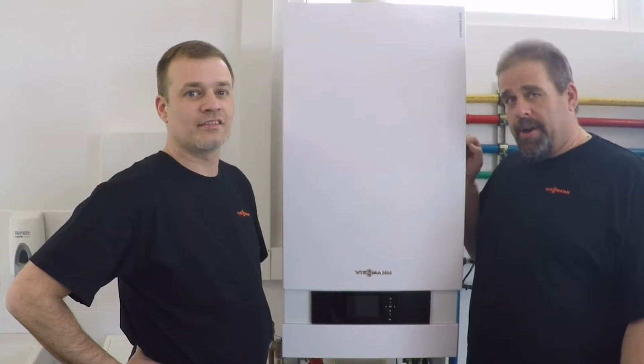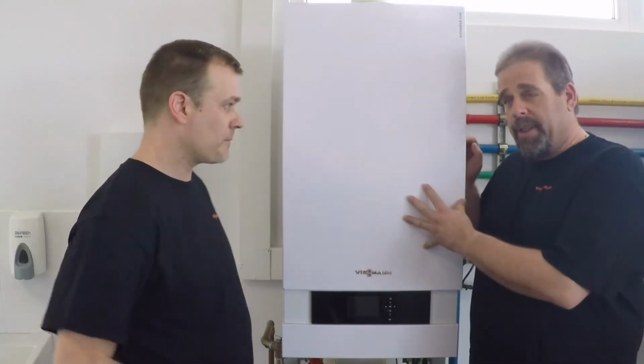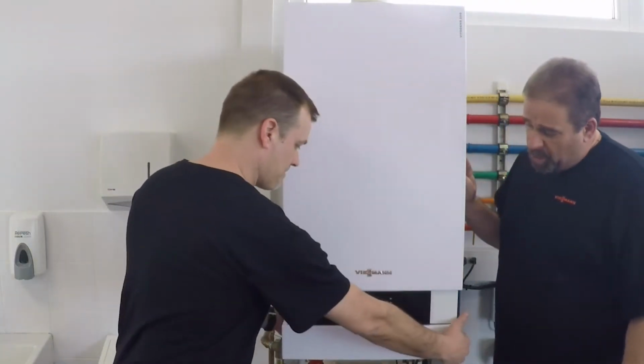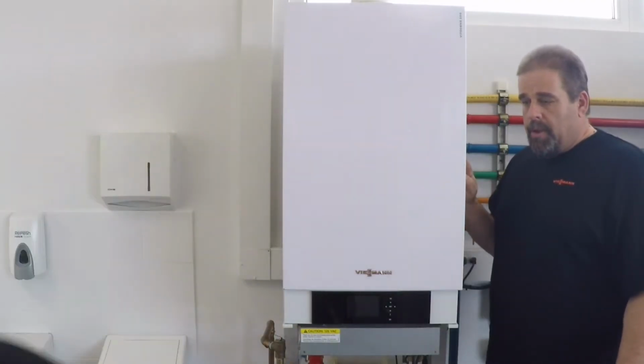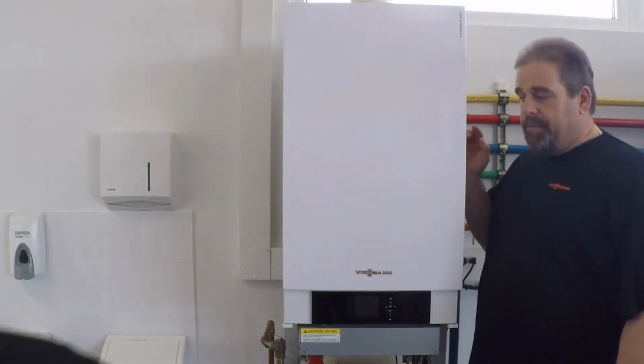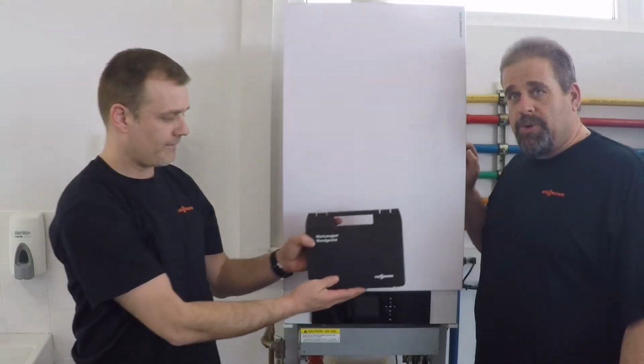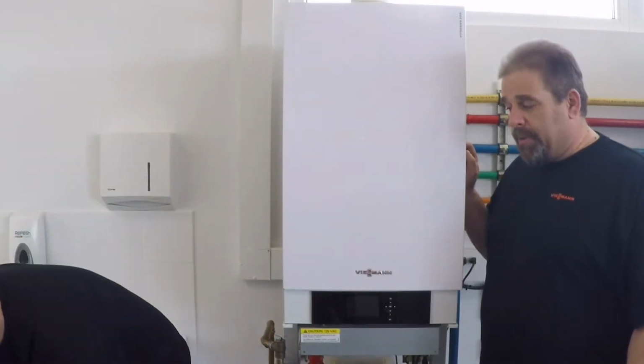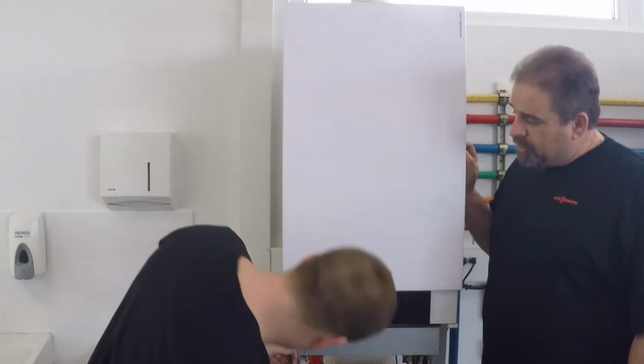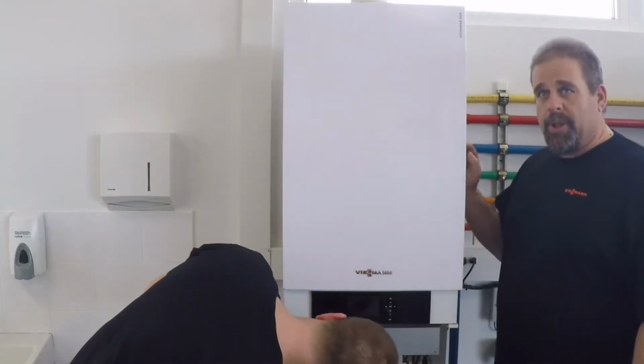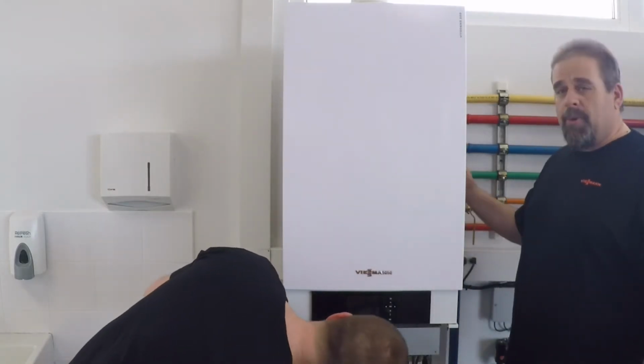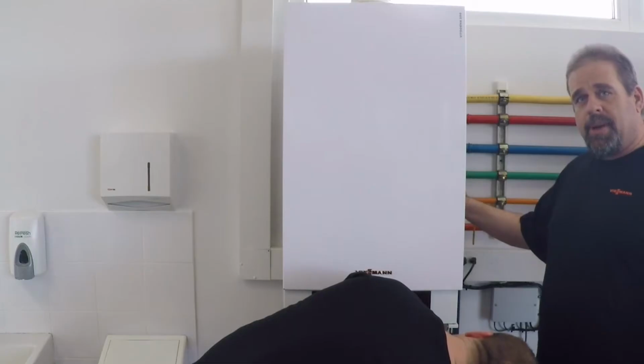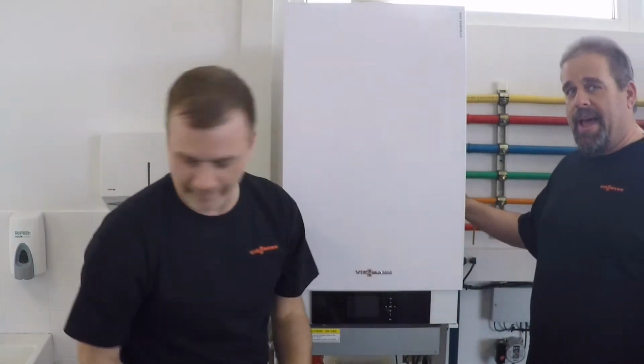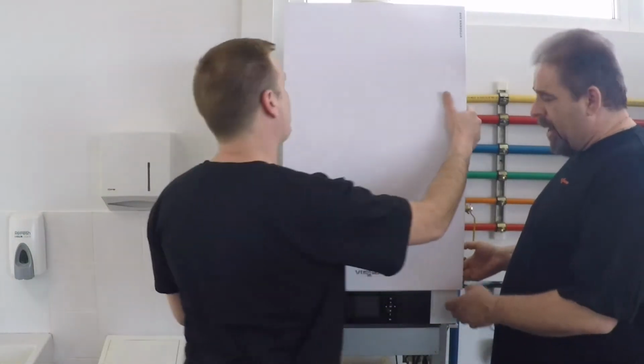Okay, so to get started, we're going to remove the cover from the boiler. To do that, we'll remove the bottom skirt. And then using our Vitodens kit with a Phillips bit and the screwdriver handle, Jay is going to show you how to remove the top cover by loosening 2 set screws up underneath this boiler pan. We need to remove the set screws because we want to make it somewhat difficult for the homeowner to be able to access the inside of this boiler.